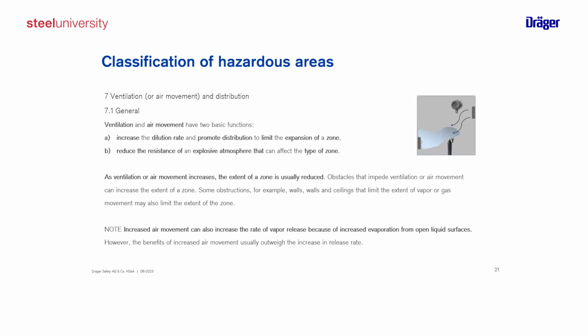Important is also to consider if you are talking about liquids, vapor. So if you increase the ventilation rate here, so with a higher airstream, you will also increase the evaporation of your liquid. The evaporation always depends on the temperature, or what we call the flash point of a substance. So depending on the flash point and the pressure, the liquid will vaporize. You will have a vapor, but this vapor will be blown away by your ventilation. And if you increase the ventilation rate, the vapor has a chance to build up much faster.